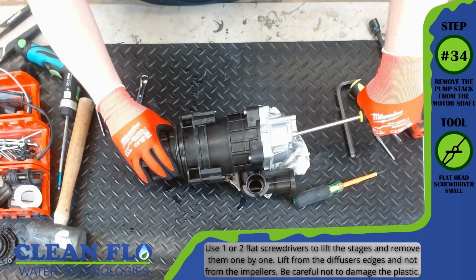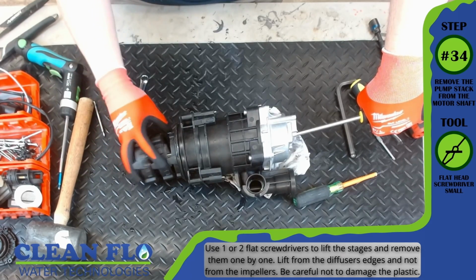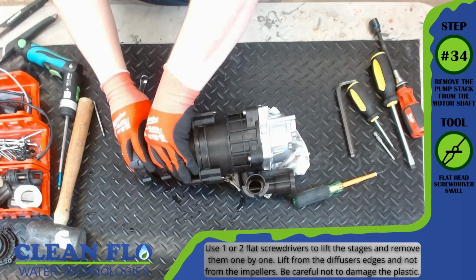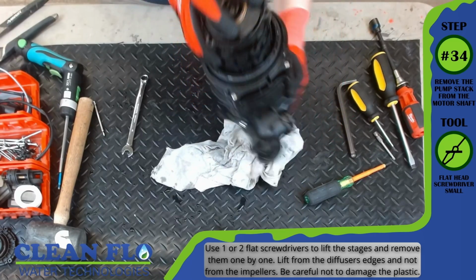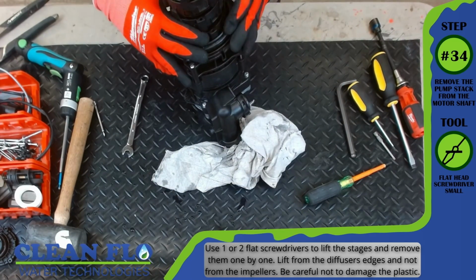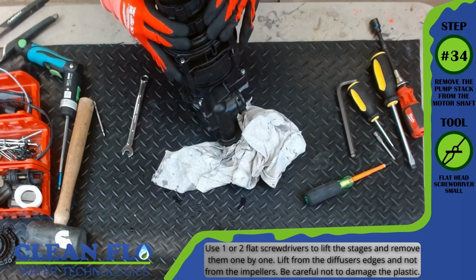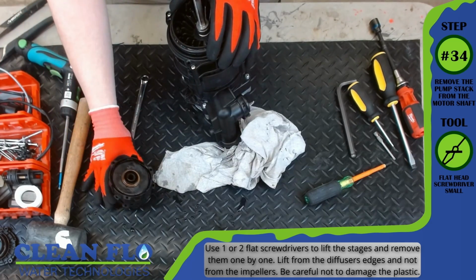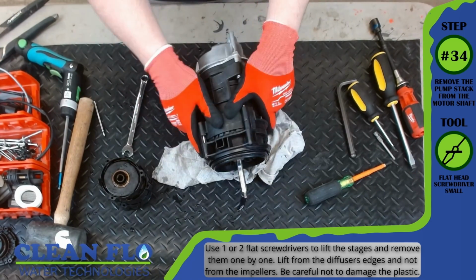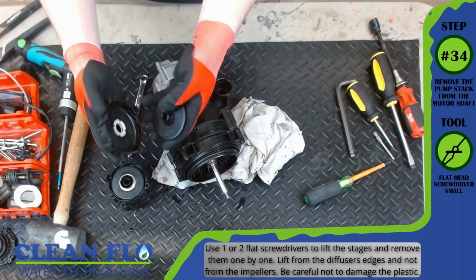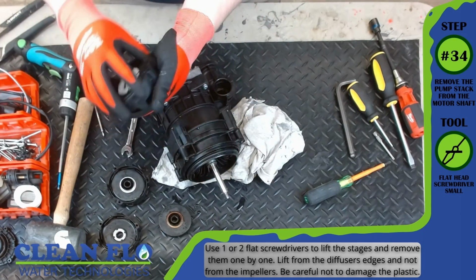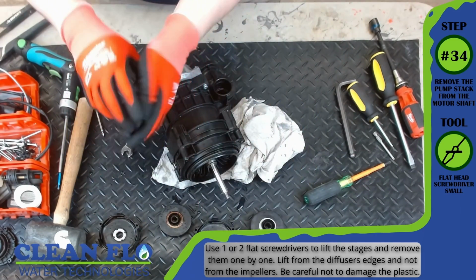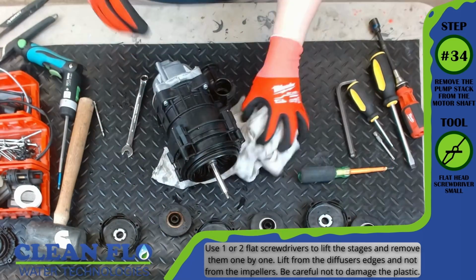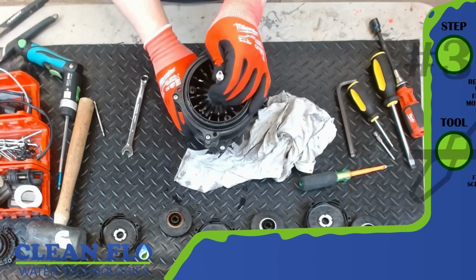Step 34, remove the pump stack from the motor shaft. Tool, small flathead screwdriver. Use 1 or 2 flathead screwdrivers to lift the stages and remove them one by one. Lift from the diffuser edges, not from the impellers. Be careful not to damage the plastic. The impellers are the components inside the stack. You should be prying on the stack, not the impellers.